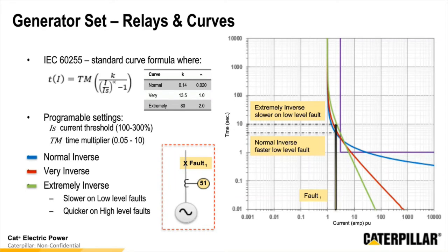So what this would do is, by making the selection of which curve you want to use, you are determining how long you want to be able to provide that current during the overcurrent on the left side of that curve. We're seeing that if we were to go with the normal inverse, we would end up with the roughly 5 seconds that we discussed earlier for that 200% overcurrent. If we were to use the extremely inverse in this situation, we would end up with 10 seconds of overcurrent during this application. So by choosing which curve we want and how we set those settings within the curves, it determines how much current we're going to see and for what duration we will see that current.